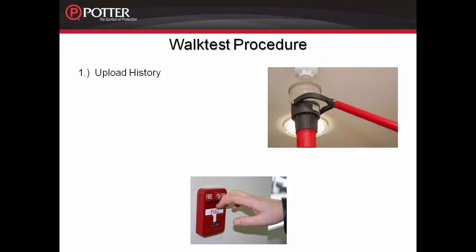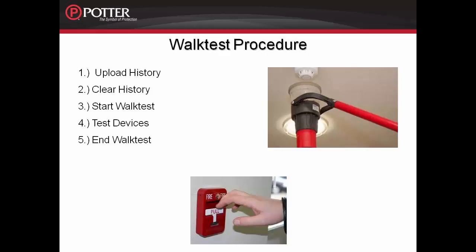To recap the walk test procedure: first, upload the history to maintain an event log, then either print or save the history file. Next, clear the panel history. After clearing the history, start walk test and test all system devices. When finished, end walk test at the fire alarm control panel. Then upload the panel history to create a test report and either print or save this file. The last step is to clear the history at the fire alarm control panel. The panel is now set until the next inspection.